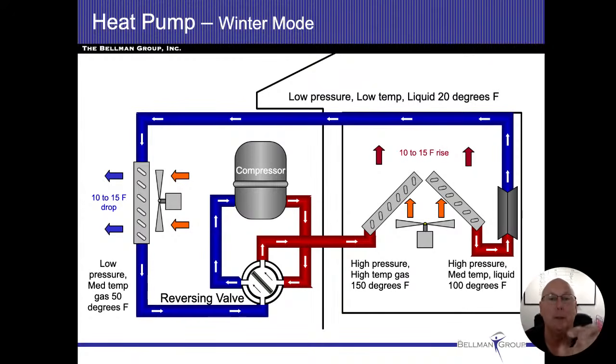So right now, this is in winter mode. So right now, we're absorbing heat from the outside, and we're bringing the heat to the inside of the house. I do want you to take note of the temperature rises, all right? And if anybody's ever dealt with a heat pump before, it's pretty difficult to say, is this thing actually working, you know? It's only a 10 to 15 degree temperature rise.